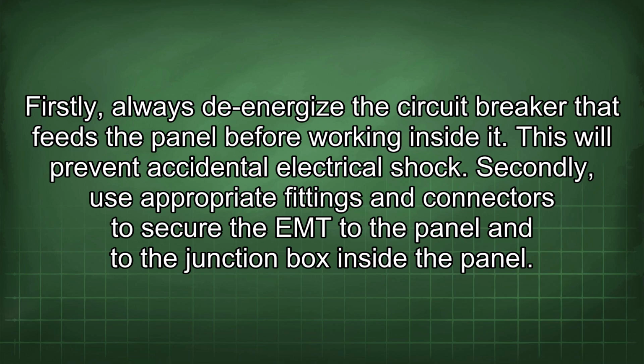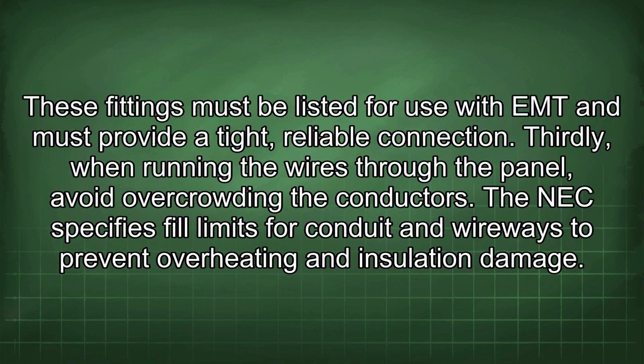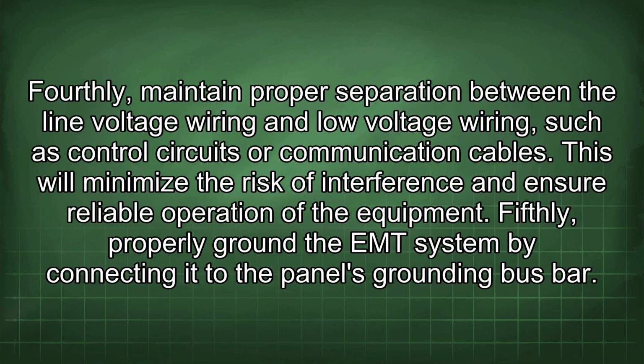Secondly, use appropriate fittings and connectors to secure the EMT to the panel and to the junction box inside the panel. These fittings must be listed for use with EMT and must provide a tight, reliable connection. Thirdly, when running the wires through the panel, avoid overcrowding the conductors. The NEC specifies fill limits for conduit and wireways to prevent overheating and insulation damage. Fourthly, maintain proper separation between the line voltage wiring and low voltage wiring, such as control circuits or communication cables. This will minimize the risk of interference and ensure reliable operation of the equipment.